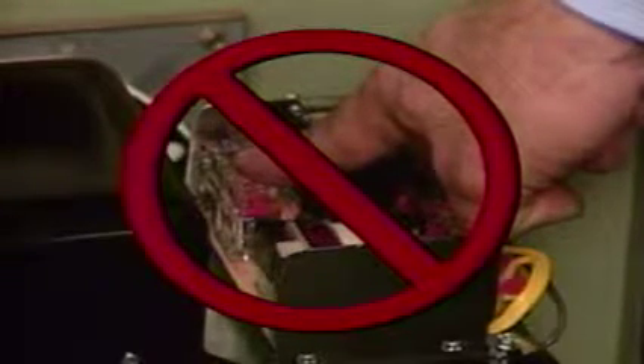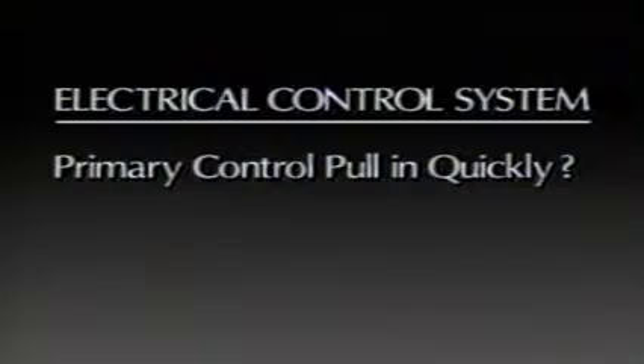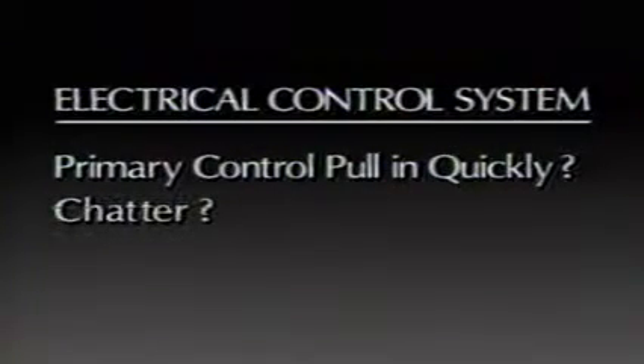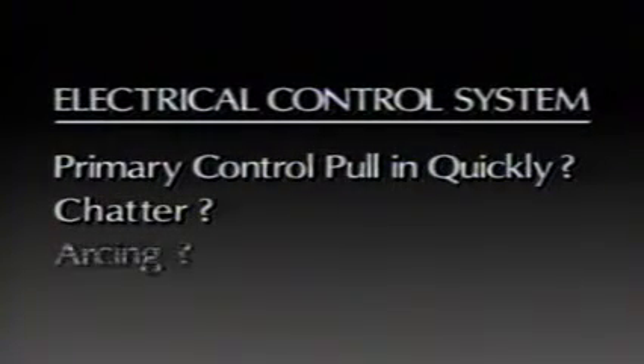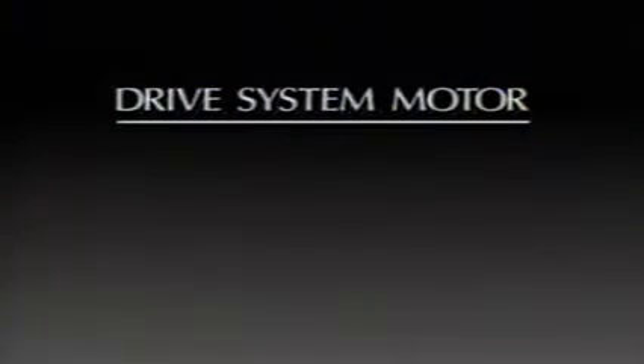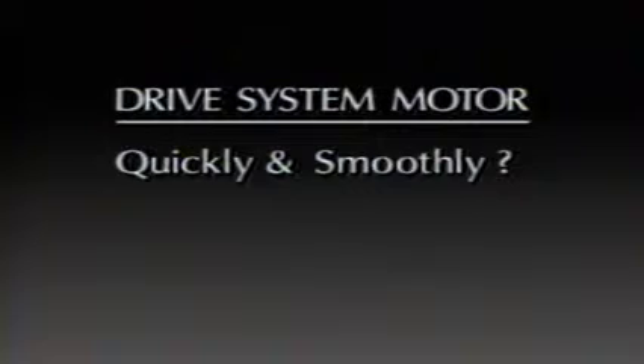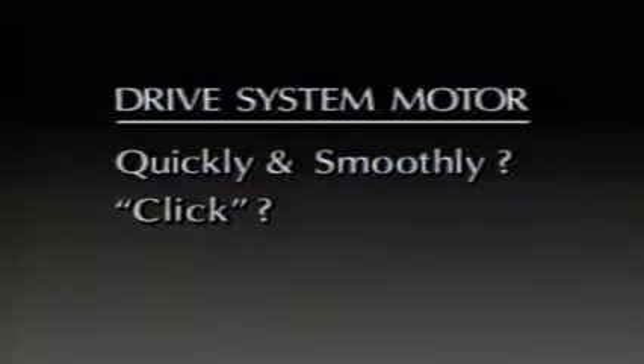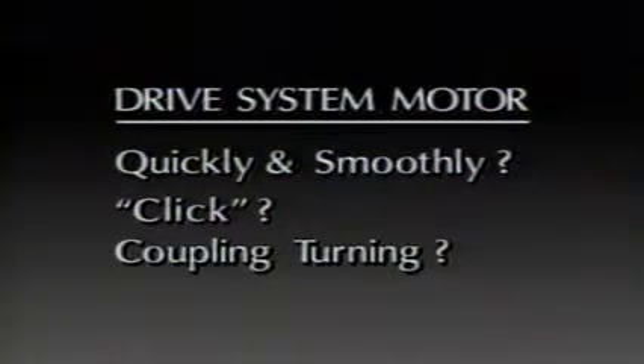To make it easier for you, we're going to examine the 4 basic systems. First, the electrical control system. Does the primary control pull in quickly? Is there any chatter or erratic arcing? Second, the drive system motor. Does it pull up quickly and smoothly? Do you hear the RPM change and a click as the centrifugal switch disconnects the starting winding? Is the coupling turning and driving the pump shaft?